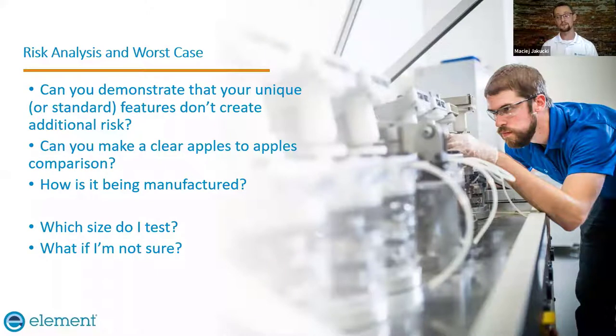Another example comes up with bone plates. A lot of times folks will assume their device is strong enough and going to pass, which is never a good idea. In some cases they'll assume it so much that they jump the gun and start manufacturing parts, then realize the spec has certain criteria because they didn't read the spec. Telling the FDA that these are the parts we have and this is what we had to test because that's what we manufactured really isn't a justification that's going to fly. So make sure when you're doing your analysis, you understand the scope of the spec, because there might be unique requirements you need to consider in your manufacturing process as well.